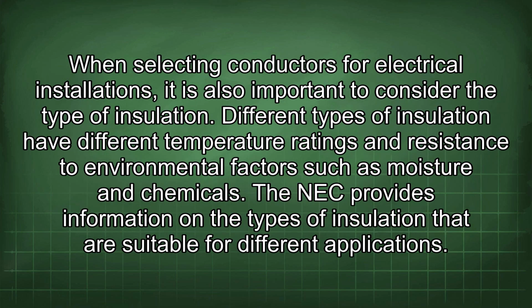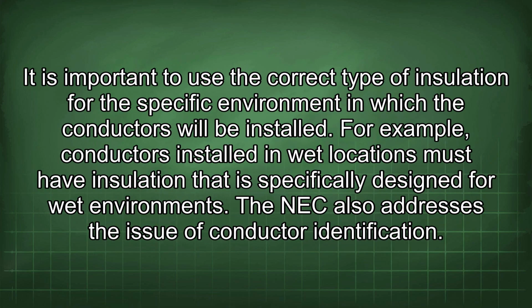When selecting conductors for electrical installations, it is also important to consider the type of insulation. Different types of insulation have different temperature ratings and resistance to environmental factors such as moisture and chemicals. The NEC provides information on the types of insulation that are suitable for different applications. It is important to use the correct type of insulation for the specific environment in which the conductors will be installed. For example, conductors installed in wet locations must have insulation that is specifically designed for wet environments.